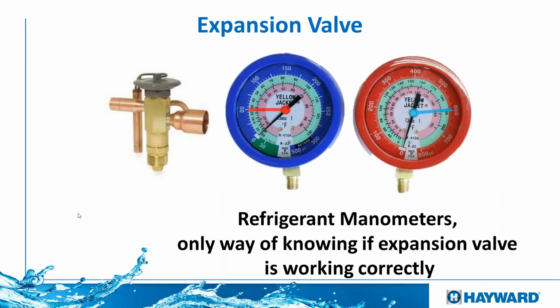Okay, and last, expansion valve. Unfortunately, the expansion valve will give you either one of these codes, either high pressure or low pressure, depending on which way the manometers move or which one moves quicker. But the only way to know if the expansion valve is bad is by putting gauges on. The gauges will tell you when the expansion valve is stuck closed and it's just not working anymore.